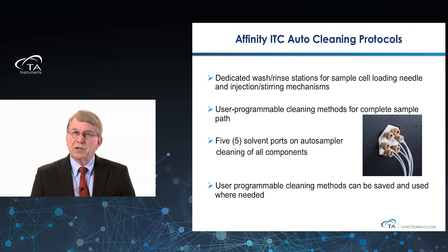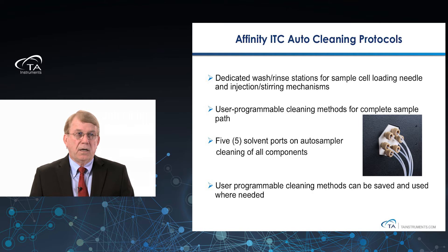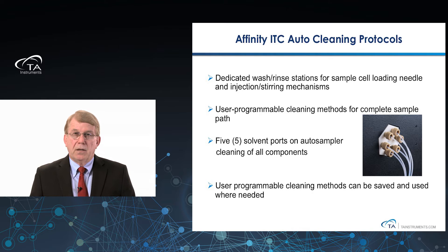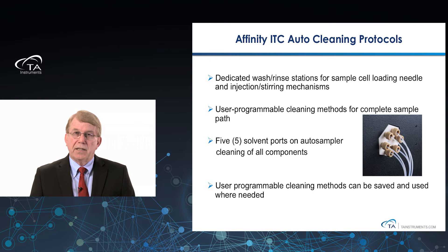For the autosampler cleaning protocols — the most common question is how do you clean the entire system. There are dedicated wash and rinse stations for both the cell loading needle and the injection and stirring system. The user can program cleaning methods for the complete sample path, all the way through the autosampler and through the cells to the waste port on the instrument. You have a choice of five solvents, with access ports on the side of the autosampler, so you can clean from the tip of the liquid handling needle all the way to the waste port. By programming, saving the template, you can insert it anywhere you want in the sequence of running or cleaning samples.